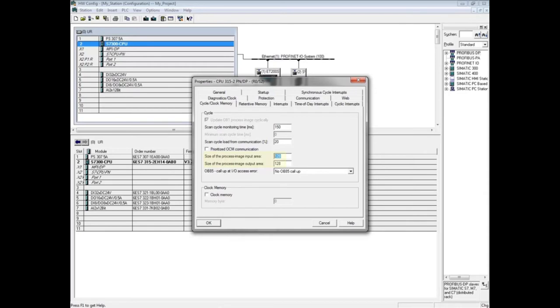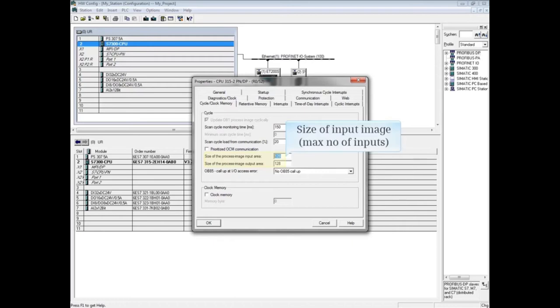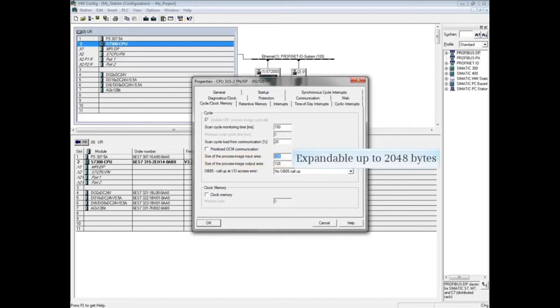The default size of the input and output process images, in other words how many I/Os you can have, is 128 bytes or 1,024 bits. By default, on newer CPUs such as this one, the size of the process images can be expanded up to 2,048 bytes or 16,384 bits.